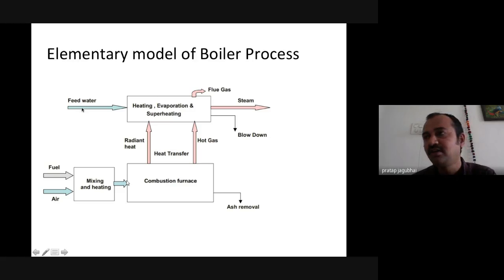Then the water. In the water, there are hard dissolved solids like magnesium, calcium and potassium, and to some level sodium also. These hard particles, or hard silica level we can say rather, are getting settled due to the makeup water, which is water we are taking, whether in the form of ground soft water or through RO water, or we are processing something on the water side to make it cleaner. This water is carrying the TDS level, and that TDS is getting settled inside the boiler drum, and we need to remove it periodically by giving the blowdown into the blowdown pit. So that TDS is getting removed.